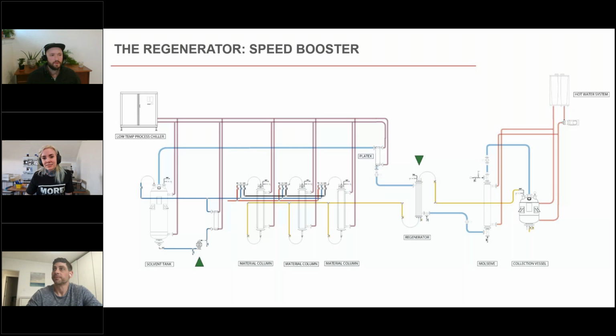Just so people aren't misled by the liquid pump, we're using one rated for -60, properly built and redesigned with special diaphragms to handle low temperatures. Not any diaphragm pump will work, and you don't want one that's not rated. Material compatibility is another important thing to consider—most diaphragm pumps have a diaphragm that's not compatible with butane.